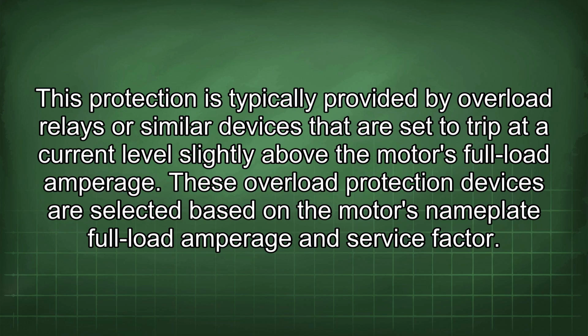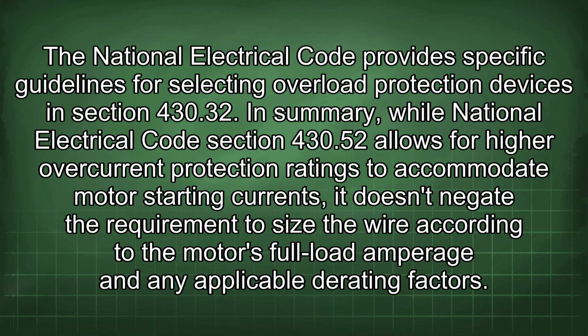These overload protection devices are selected based on the motor's nameplate full load amperage and service factor. The National Electrical Code provides specific guidelines for selecting overload protection devices in Section 430.32.